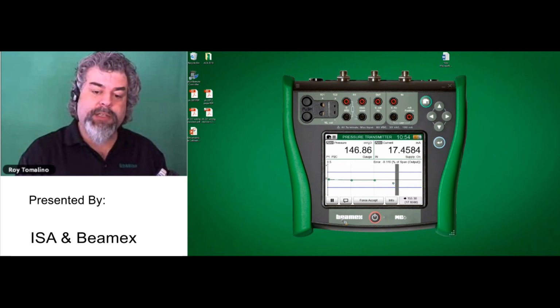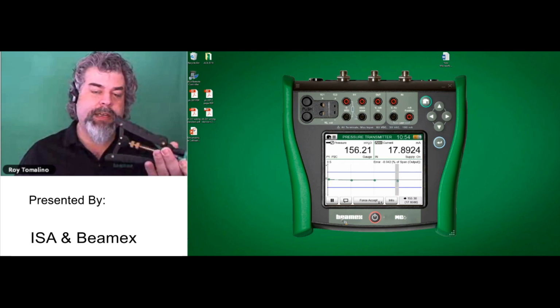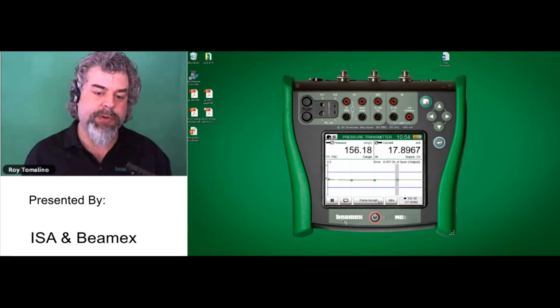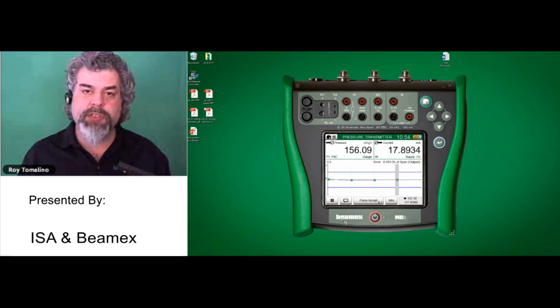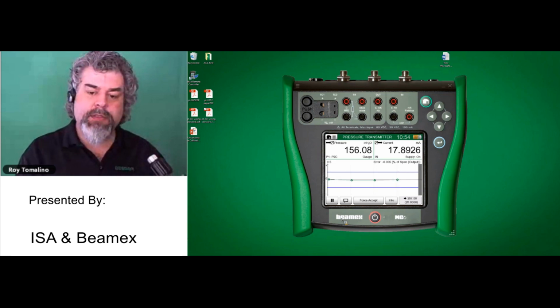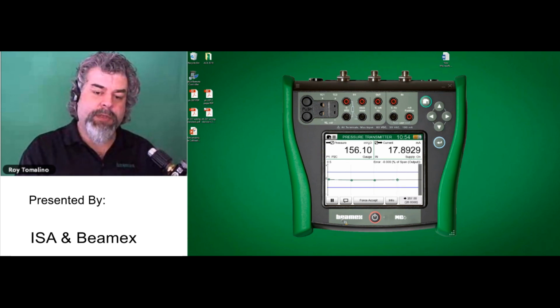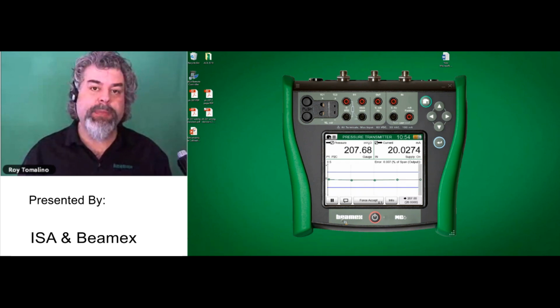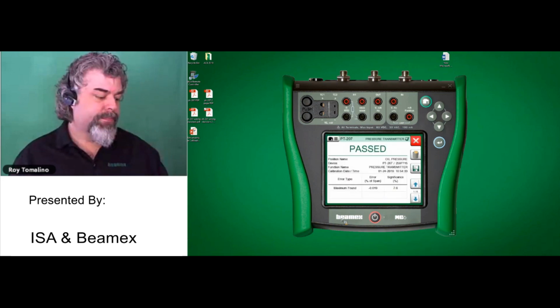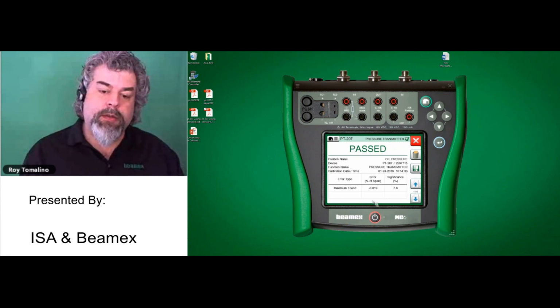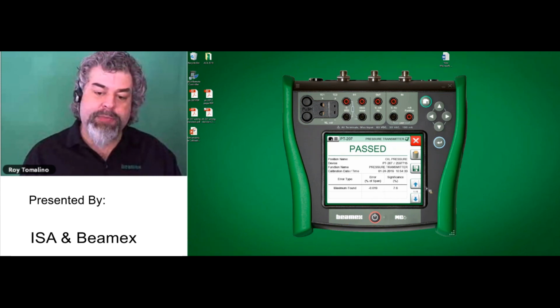So let me grab my next test point. Again, I'm just squeezing gently on this pressure pump. I could be using the fine-tune knob, but if I can do it through the normal method, I'll do that. Okay, so I overshot it a little bit, but that's okay. My maximum error was 0.019% of span.